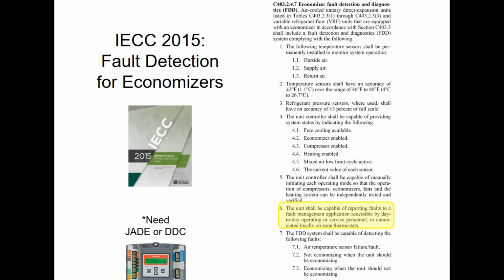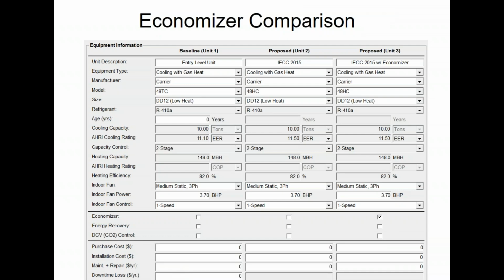If you don't have a BAS, then your alternative is to display the alarm on the thermostat itself. But you need to have that FDD monitoring, and you need to report it down into the space to either the building managers or the occupants in some way. That's kind of a big change from previous codes, kind of a unique thing.